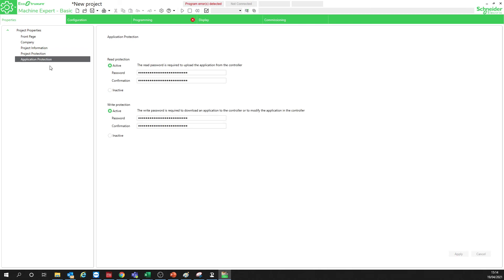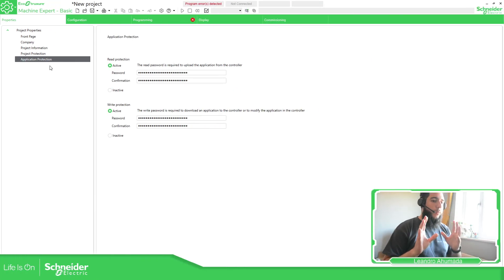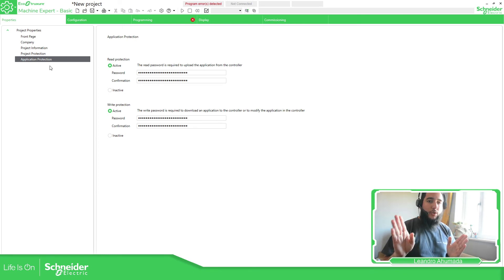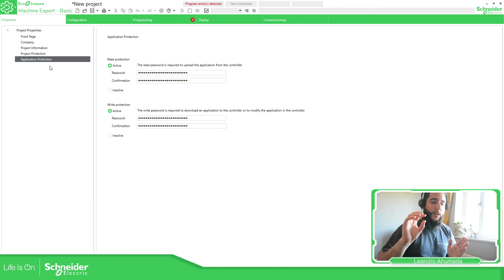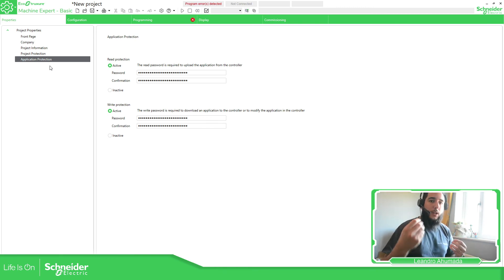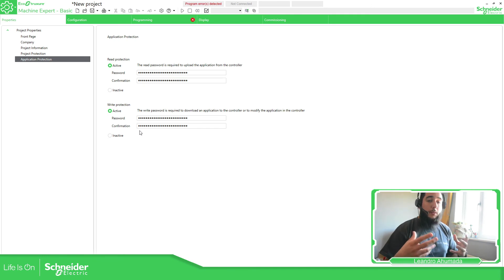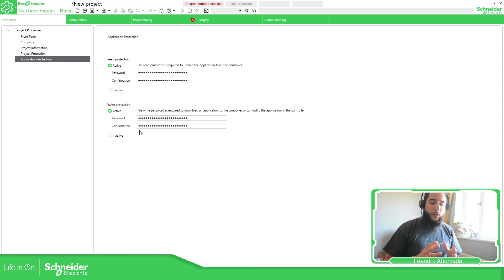And then we have Application Protection, which is more related to the physical controller — accessing the PLC. So just to recap: we have Application Protection and Project Protection. Project Protection applies when you open the project file on your laptop — the .SMBP extension — using Machine Expert Basic. It will ask for a password before you can make modifications. Application Protection is all about trying to download or upload information to the physical controller.